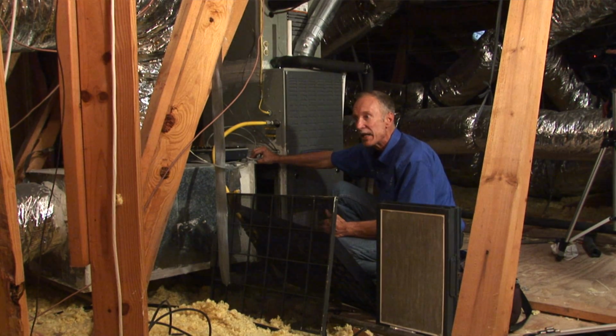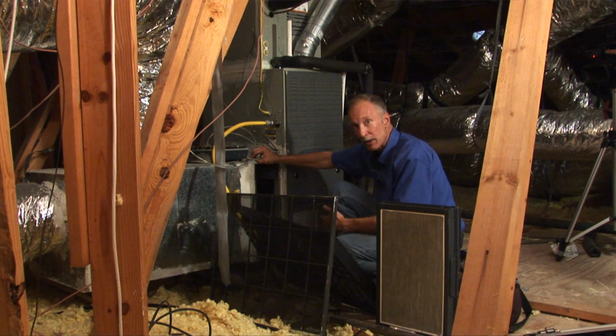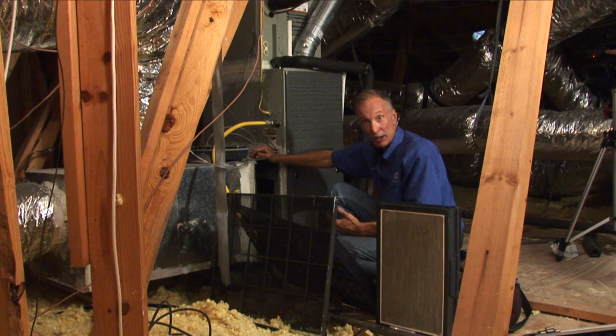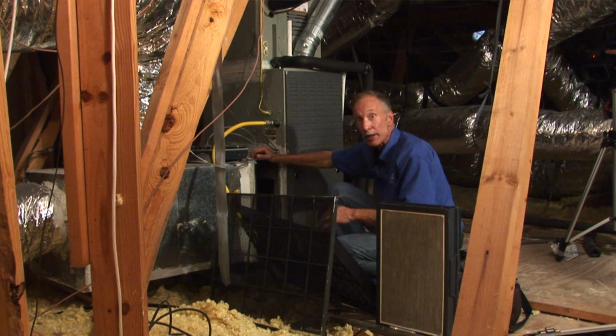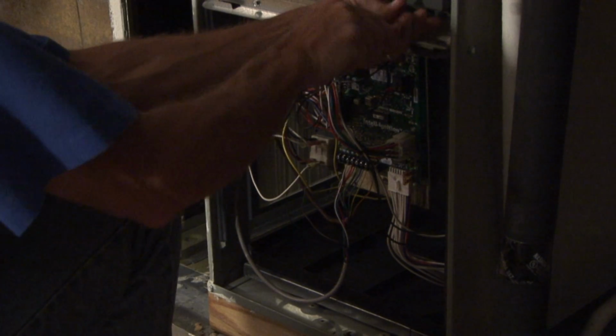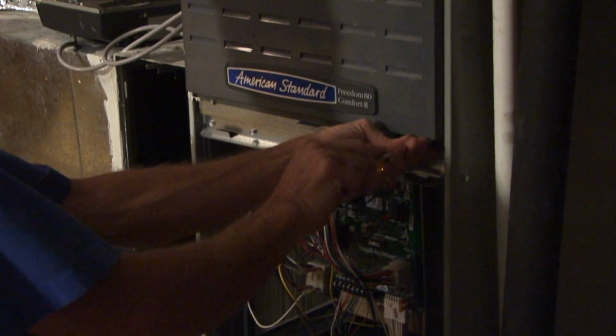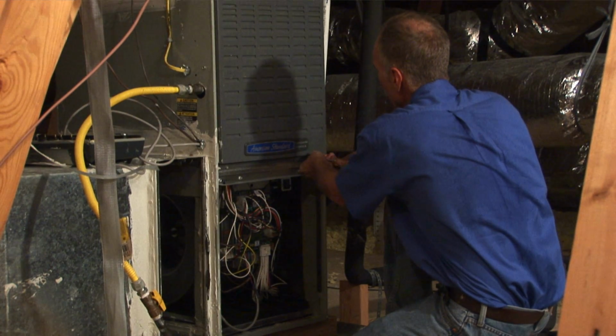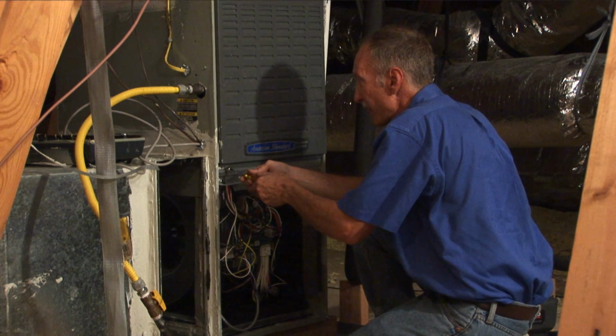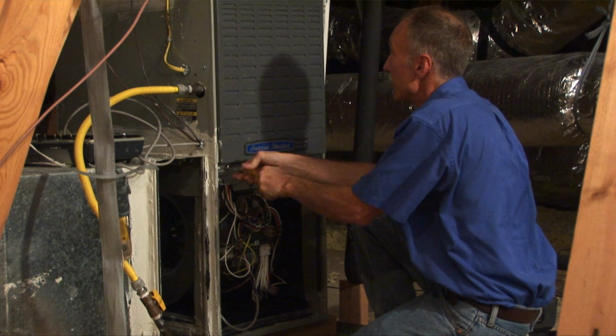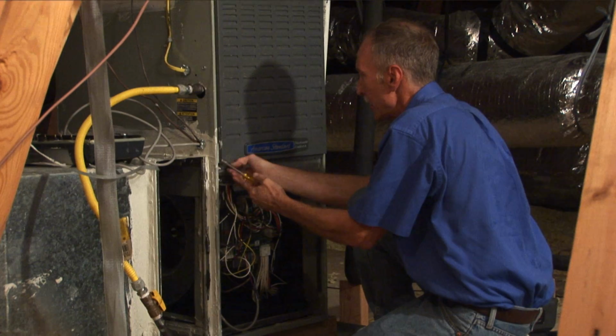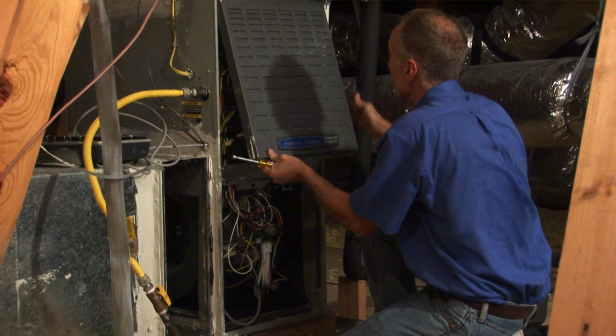A 5-inch media filter needs to be replaced every 6 to 12 months. In this case, we can just take this out and clean it. We'll return later with the clean filter and reinsert it. Next, I'll remove this panel here, and then I'm doing the visual checkup of all of the individual components in this upper compartment.